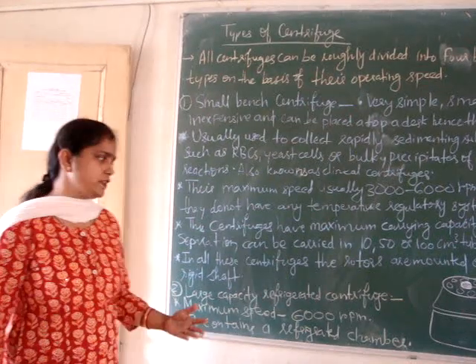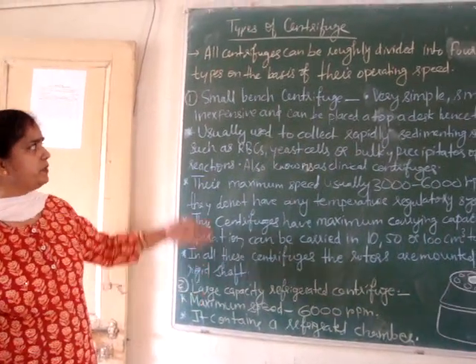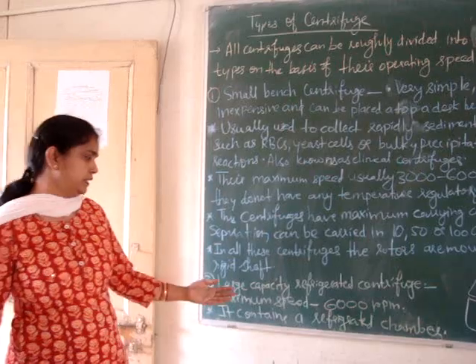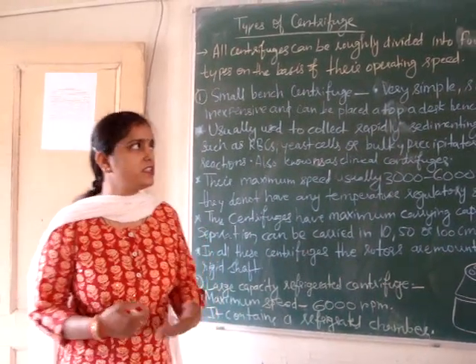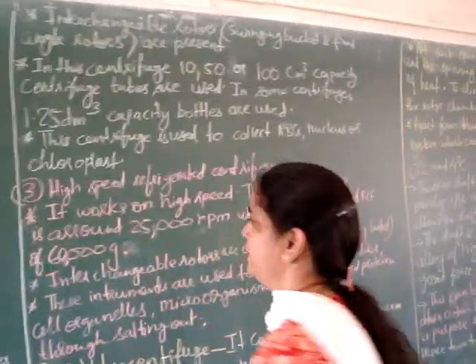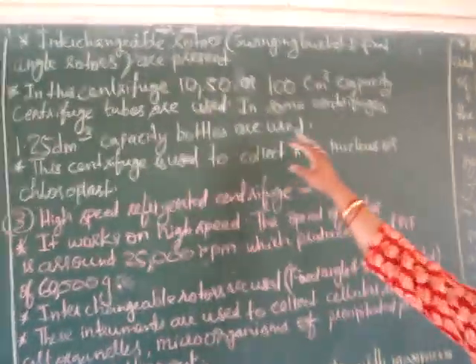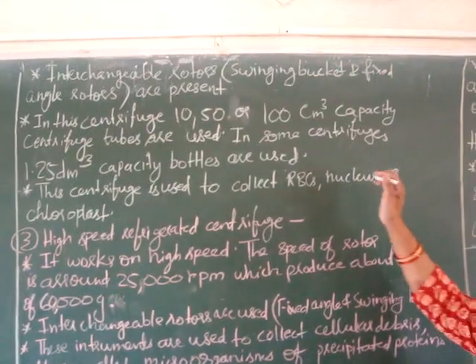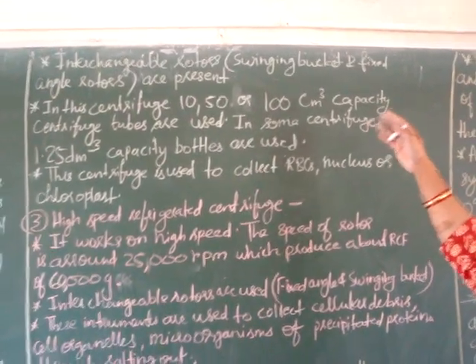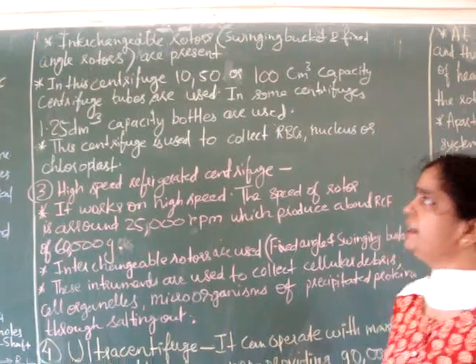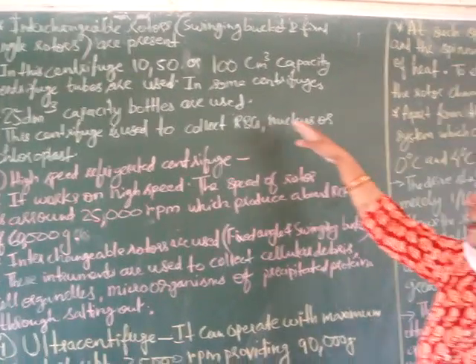The second type is the large capacity refrigerated centrifuge. Their maximum speed is the same as the small bench centrifuge, but it contains a refrigerated chamber which maintains the temperature. One more difference is that their rotors may be interchangeable — that is, swinging bucket and fixed angle rotors are both present.